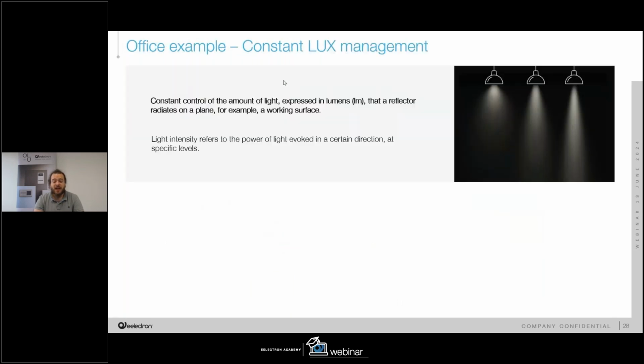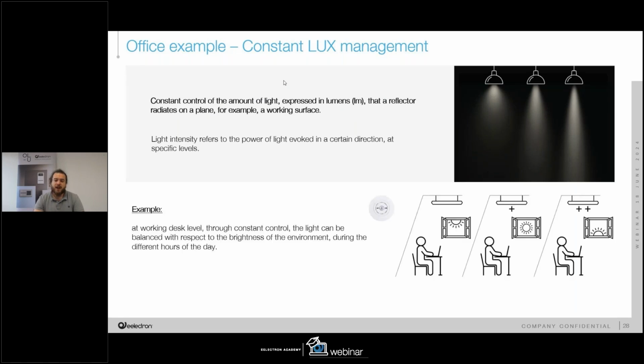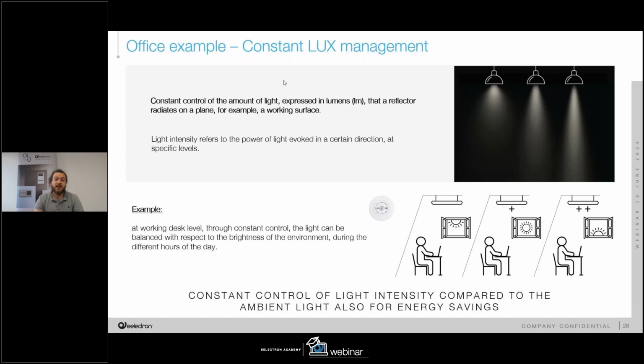Going ahead with the webinar, we want to show you one example of what we can achieve with the new DALI multi-master application controller, where we have an amount of light that the lamp can generate expressed in lumen to increase the brightness inside the room. And thanks to the presence detector plus the lux meter that is inside the presence detector, we can keep, on a desk for example, a dedicated set point, and this will be constant. A classic example is the request to keep 500 lux on the desk, and if outside is a sunny day, we have to decrease the lumen of the lamps. If it's a cloudy or rainy day, we have to increase the brightness inside the room and keep, again, the 500 lux.